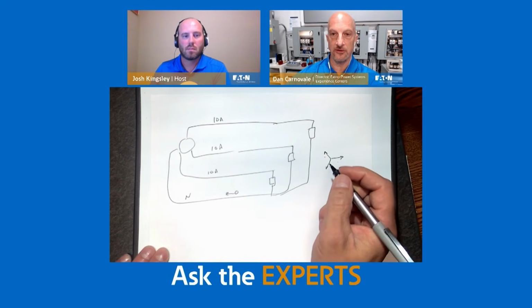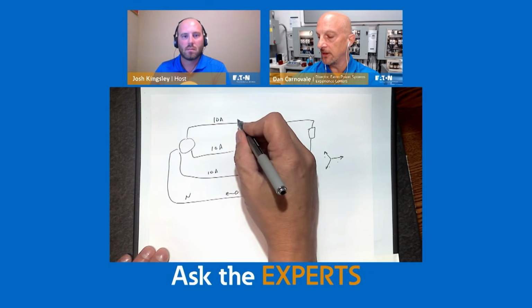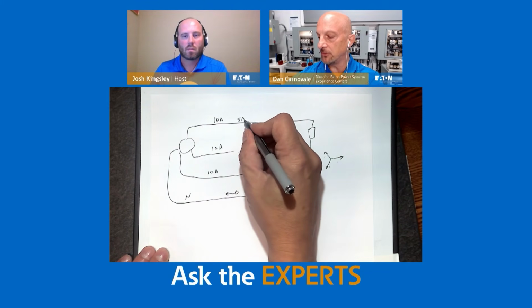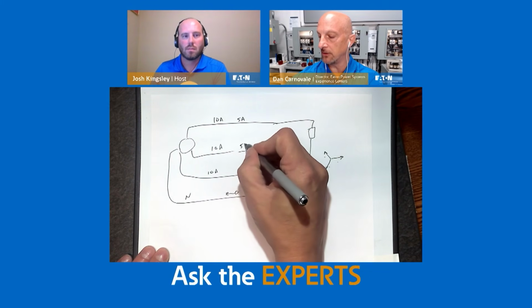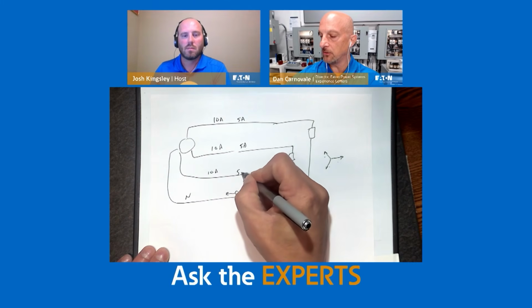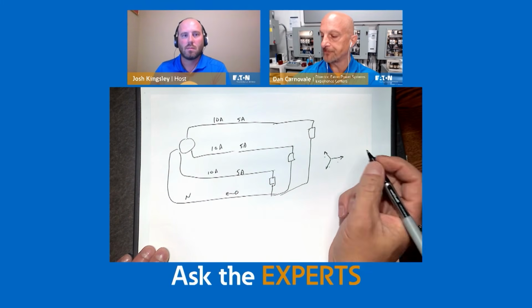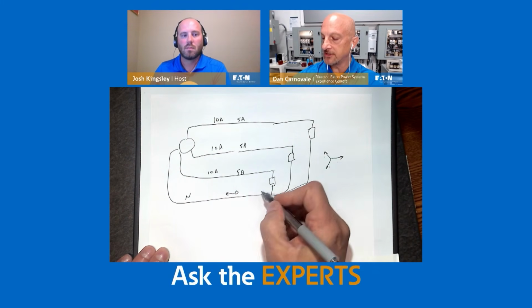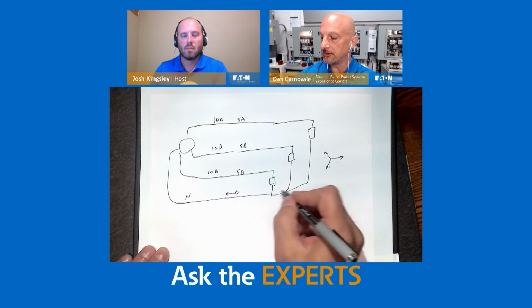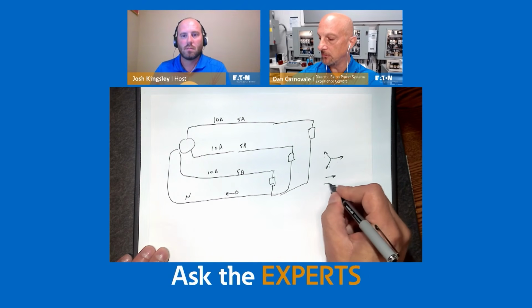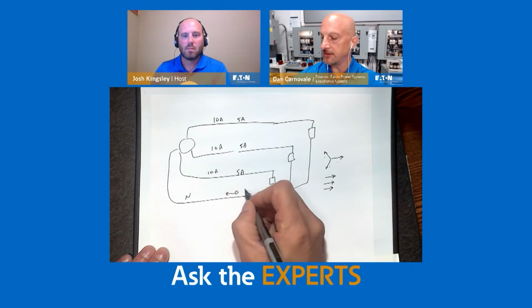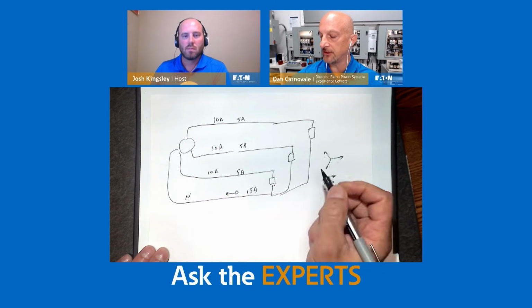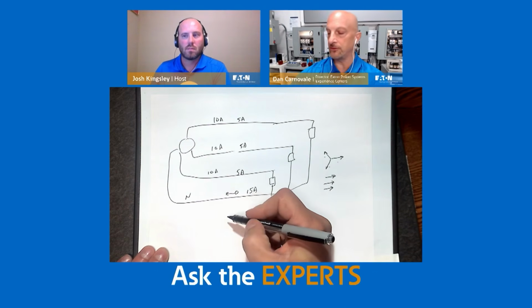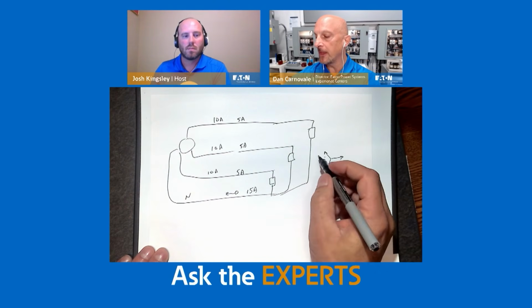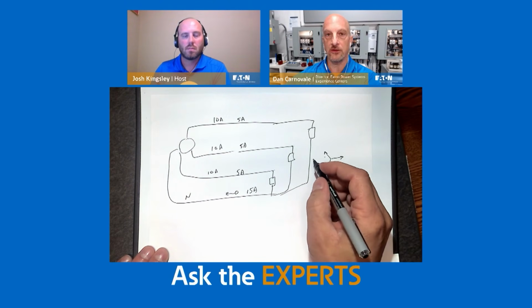But what's interesting is you mentioned zero sequence. So if I have, let's say, 5 amps or 10 amps or whatever of third harmonic or zero sequence, that current is actually additive on the neutral. And so when it gets back to this point, it's 1, 2, 3, and it adds up to be 15 amps in this case. That's why people historically have doubled neutrals and stuff like that.